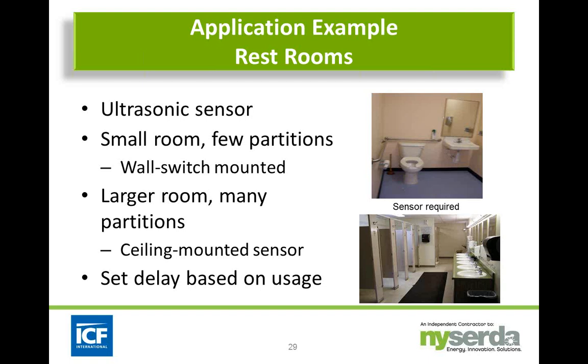So you want to make sure you've done this correctly. Set the time delay based on usage. If it's a very active space, you might want to set the time delay farther out to avoid problems with overly frequent switching. If people are coming and going fairly frequently, setting it at 15 minutes might keep the lights from turning on and off too often. Obviously, if it switches too frequently, it might reduce the life of the lamps and ballast.